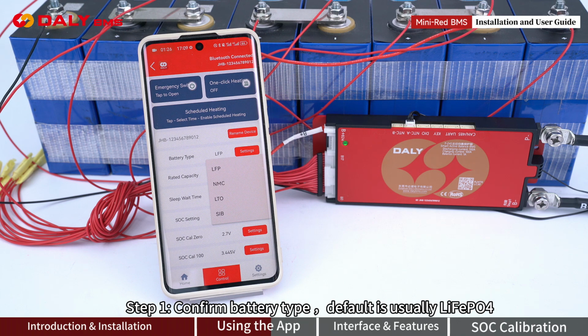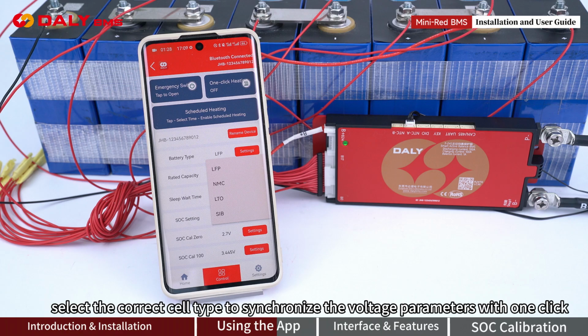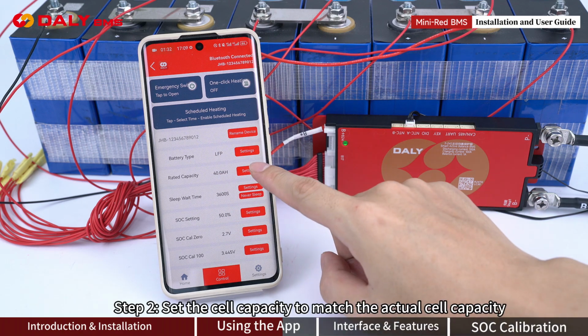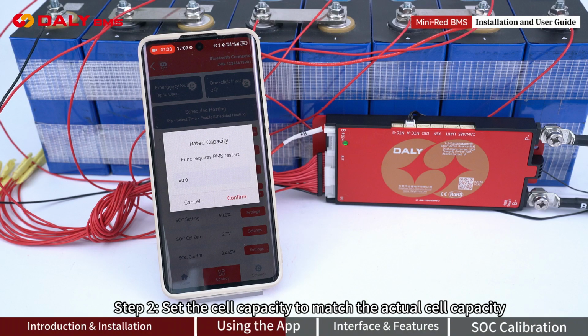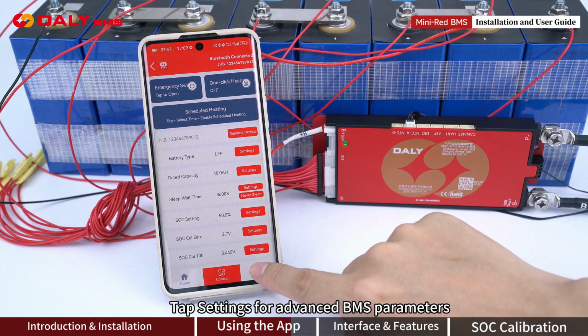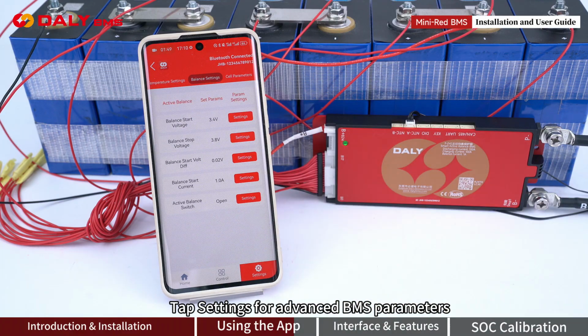Default is usually LiFePO4. If it does not match the actual battery type, select the correct cell type to synchronize the voltage parameters with 1 click. Step 2, set the cell capacity to match the actual cell capacity. Tap Settings for advanced BMS parameters.